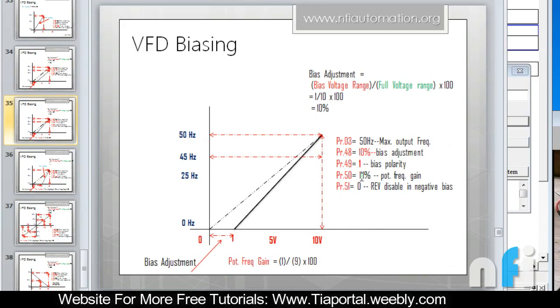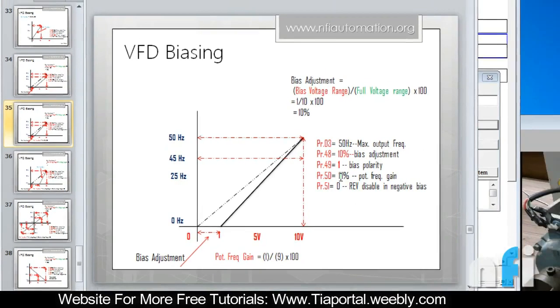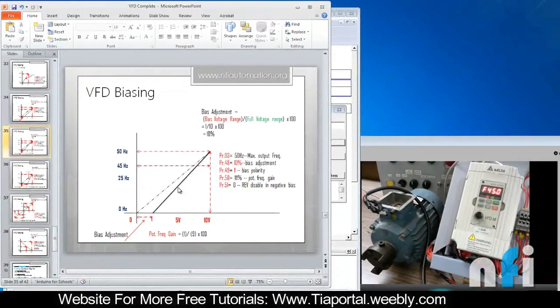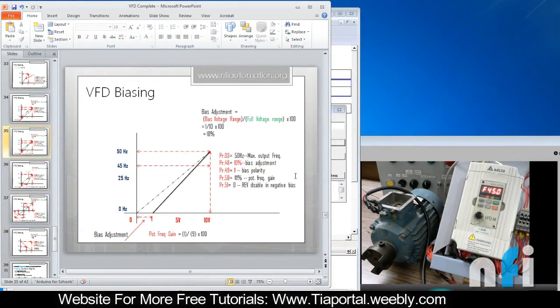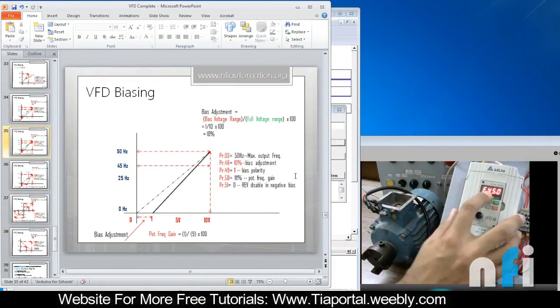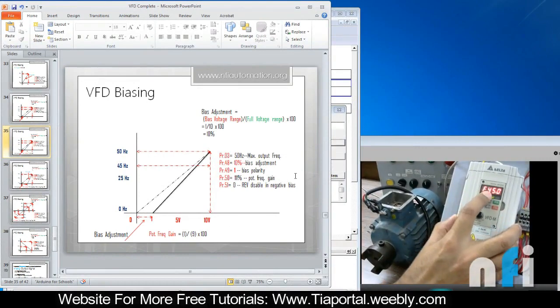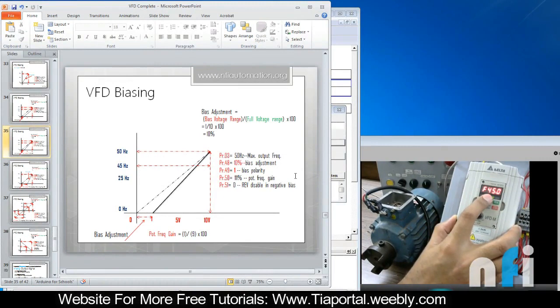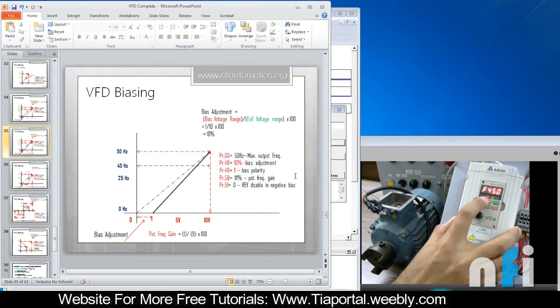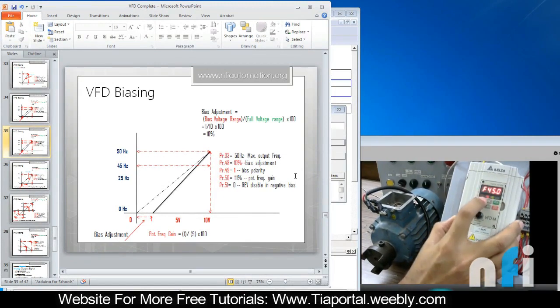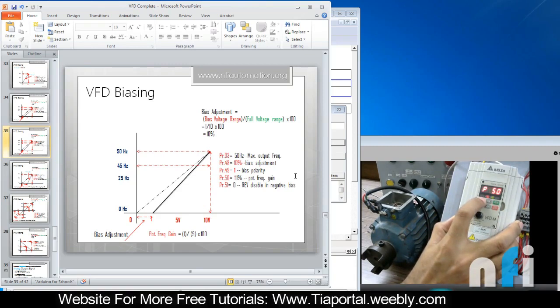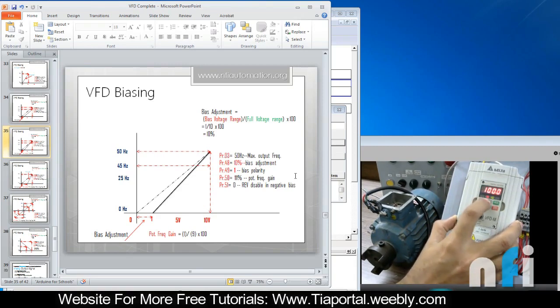This is what we have to change in our drive to achieve this result. Right now this is 45 hertz because this is 10 volt. So if I increase the potentiometer frequency gain to 111 percent I will achieve 50 hertz here. That is parameter 50.